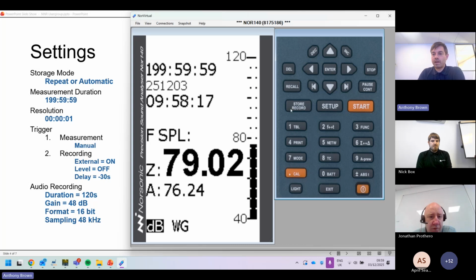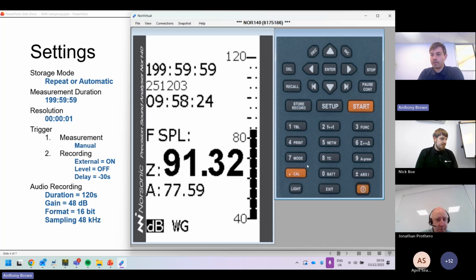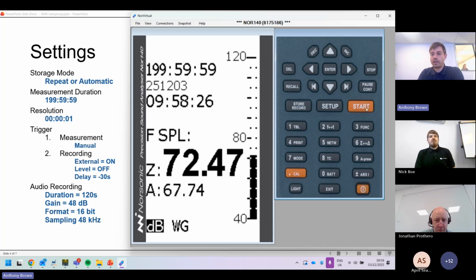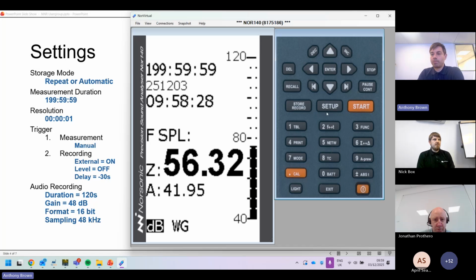So to change the settings, let's just look over the keypad. You've got some important keys: the on button, the cal button, and then the start button. This is what you'll use later. But your most important keys for the settings now are the setup key and then the enter key in the middle. Just remember this enter key is really weird on this meter, but when you want to come back out of an option, you'll normally have to press enter to go back. So remember that enter brings you back. It's a return button.